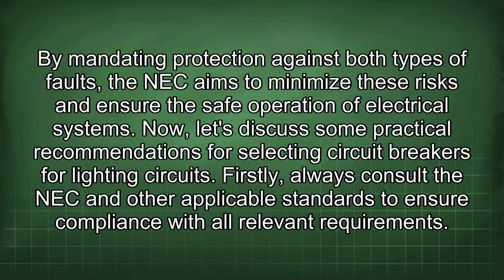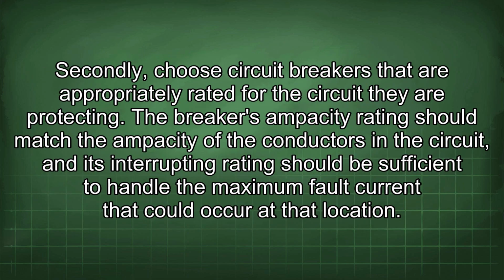Now let's discuss some practical recommendations for selecting circuit breakers for lighting circuits. Firstly, always consult the NEC and other applicable standards to ensure compliance with all relevant requirements. Secondly, choose circuit breakers that are appropriately rated for the circuit they are protecting. The breaker's ampacity rating should match the ampacity of the conductors in the circuit, and its interrupting rating should be sufficient to handle the maximum fault current that could occur at that location.